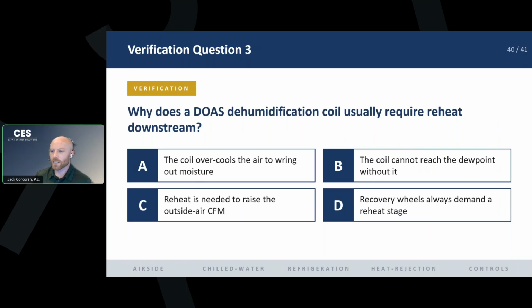And our last question: why does a DOAS dehumidification coil usually require reheat downstream? A, the coil overcools the air to wring out the moisture. B, the coil cannot reach the dew point without it. C, reheat is needed to raise the outside air CFM. Or D, recovery wheels always demand a reheat stage. I'll give you guys a second.